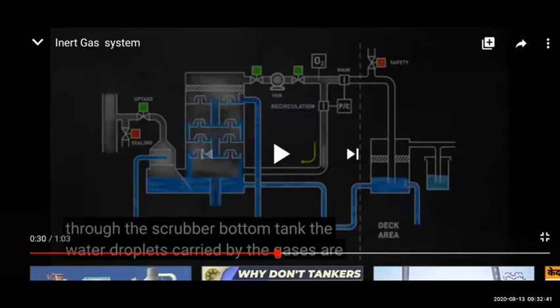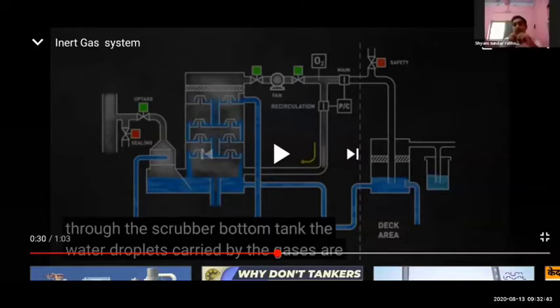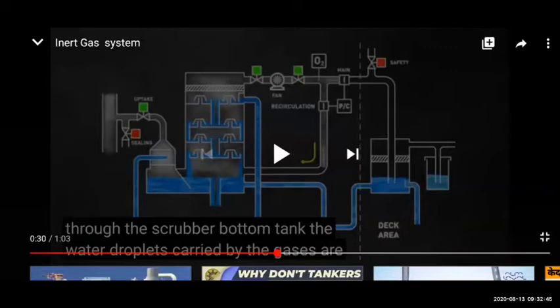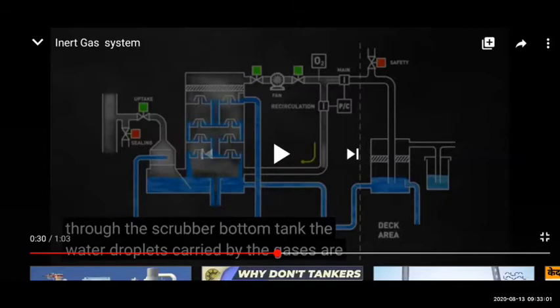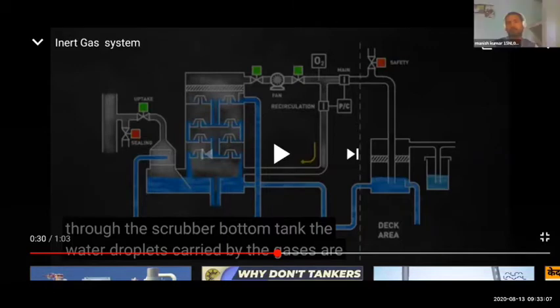The oxygen threshold is less than 5% from the inert gas plant, and for the tank it should be less than 8%. But nowadays some companies have stricter requirements of 2% or 3%. Modern inert gas plants or generators can achieve even 1% or 2% oxygen easily.